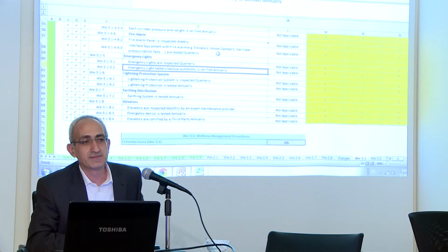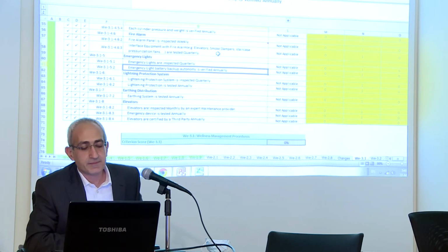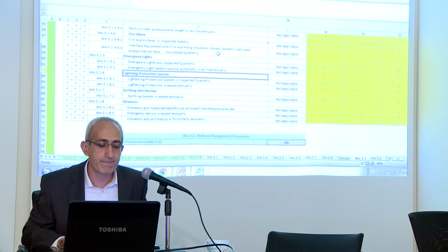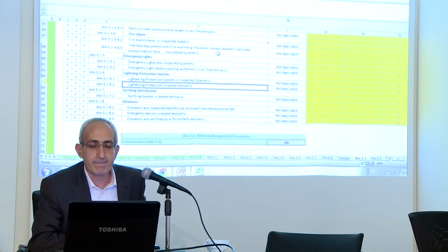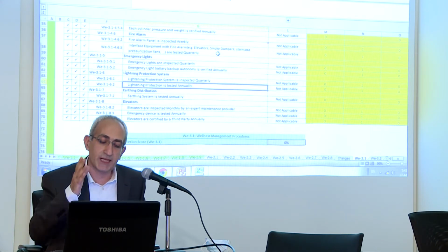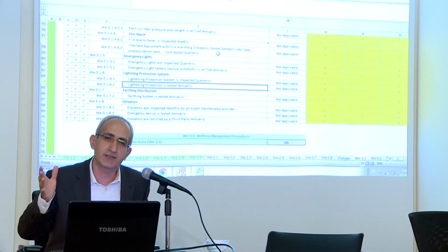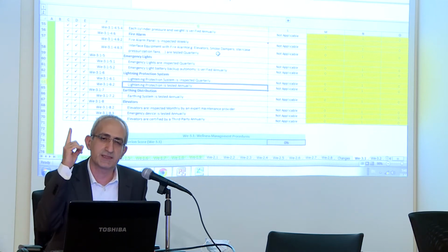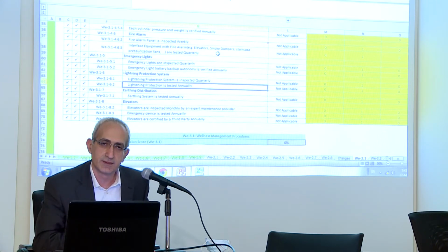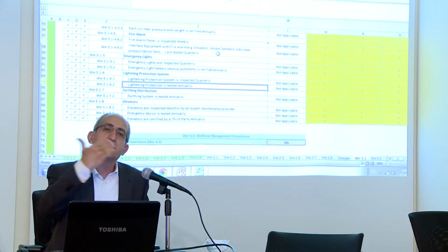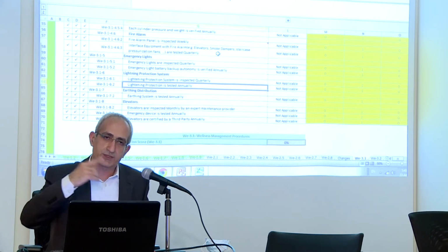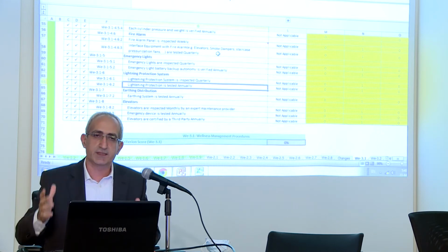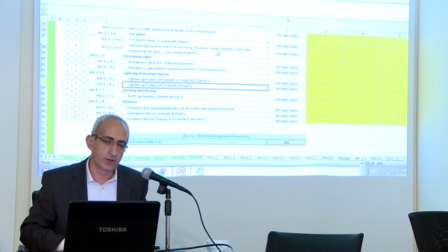I have one question here. When you are talking about lightning protection, is it necessary maybe to mention that you have a meter for strikes? Because now the new lightning protection systems have meters. Some lightning protection have meters, but the Faraday cage, I doubt they have a meter. Maybe the single probe has a meter. And if you're adopting the American lightning protection with several strikes and the Faraday cage on the building, I don't think they have a meter there.